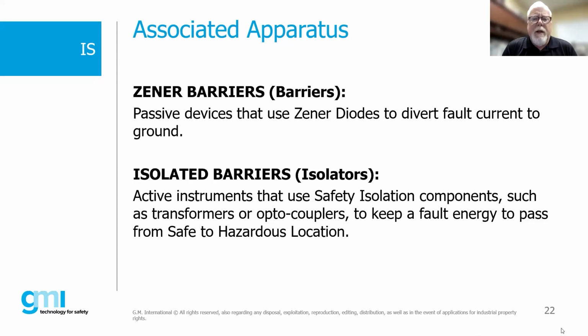Now these devices operate slightly differently. They are active instruments, they need to be powered, and they use safety isolation components, primarily a transformer or optocouplers, to keep that fault energy from passing from a safe to a hazardous location. So they're doing the same thing, they're just doing it in a slightly different fashion.